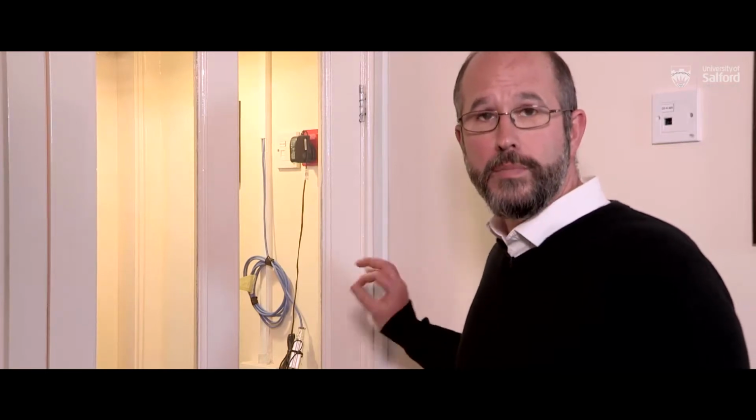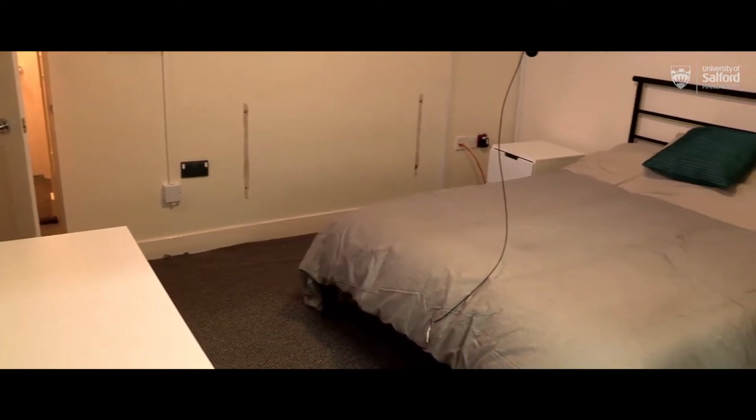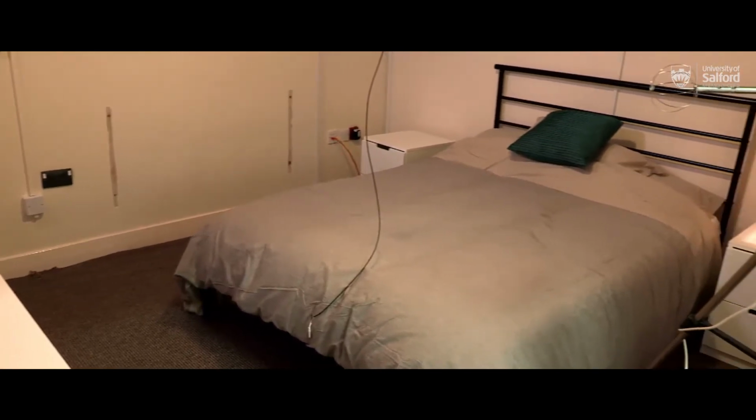At the corner of each room, at 3 different levels, and at the geometric centre of the room, we measure temperature and relative humidity. This helps us understand how an occupant in the room might experience comfort. It's important to gather this data because temperature can vary by quite a large degree from one corner of the room to another.